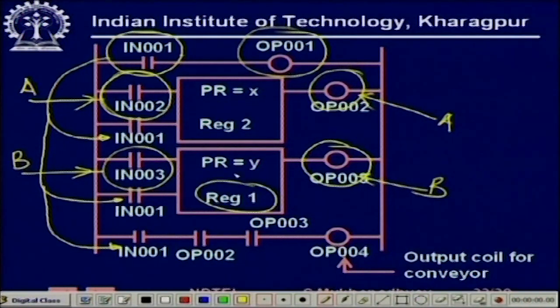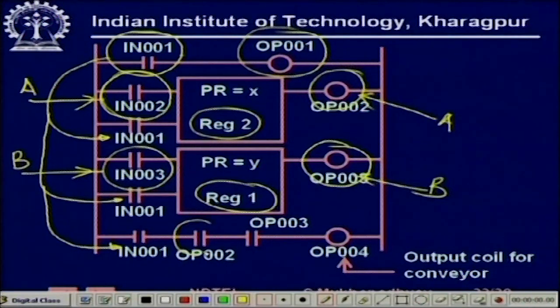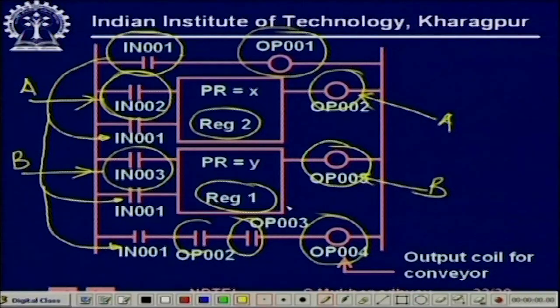The registers are incremented, not the outputs directly. When both registers cross their preset values, the outputs go high. Since they are placed in series, both must reach their preset count values before the conveyor will run. If you put them in parallel, it means that if any one of them reaches its preset value, the conveyor will run.